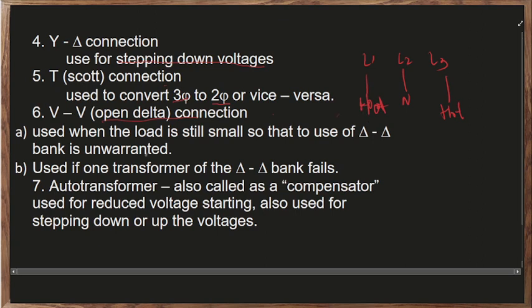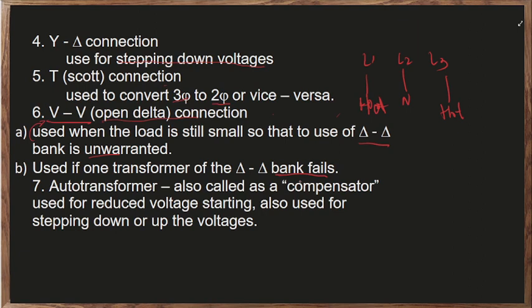The advantage is you could have a three-phase system using only two transformers, kasi dalawang transformer lang ang kailangan dito, no? So if you are needing only a three-phase system, tapos medyo mababa lang yung load mo, so mas okay yung open delta, no? So use when the load is still small, so that to use a delta to delta bank is unwarranted. So ito yung rason kung bakit nag open delta tayo. Now, also use if one transformer of the delta to delta bank fails. So kunyari nasira yung isang transformer ng delta to delta, pwede nating i-rewire yun as an open delta.